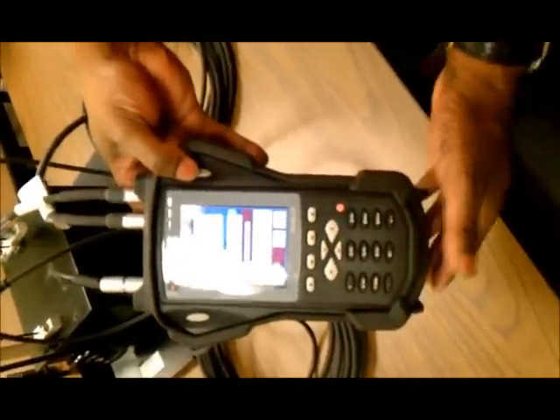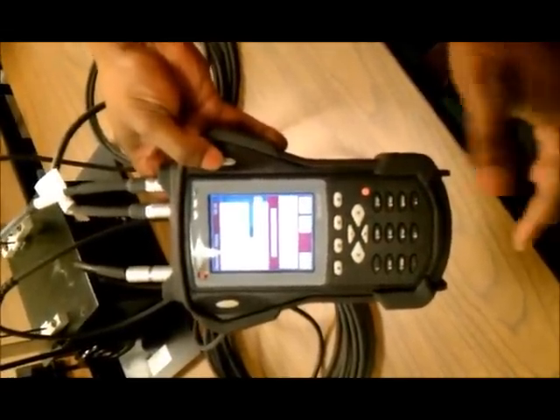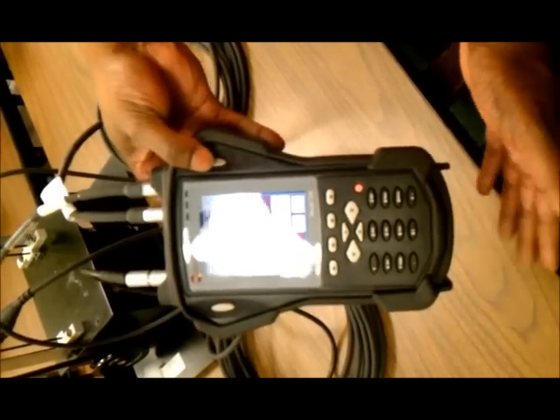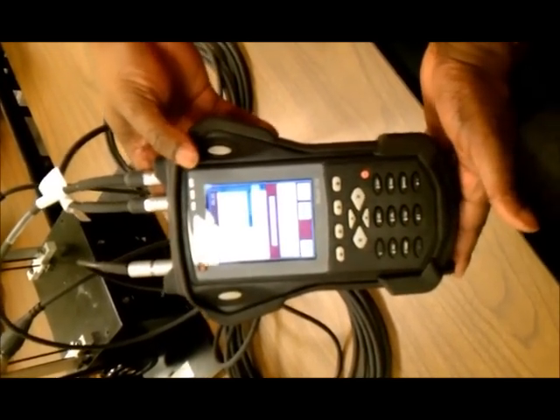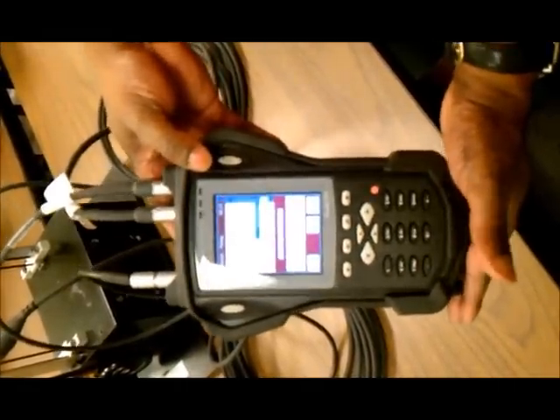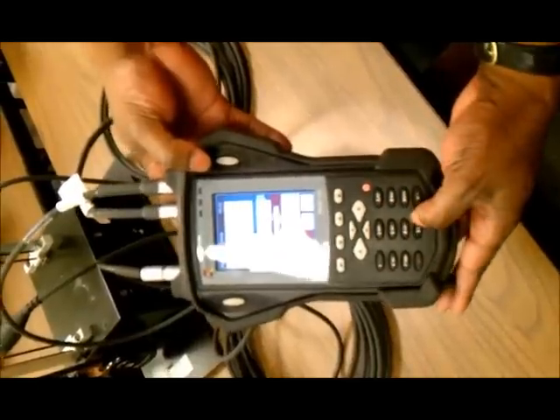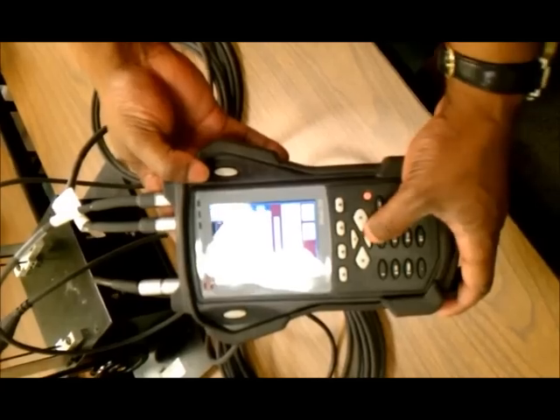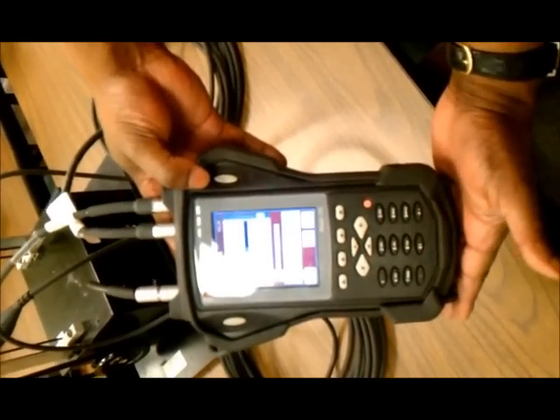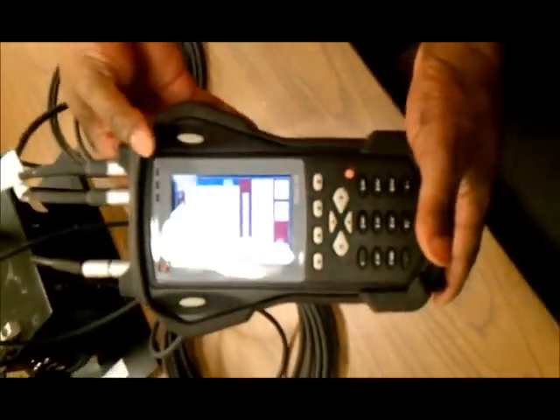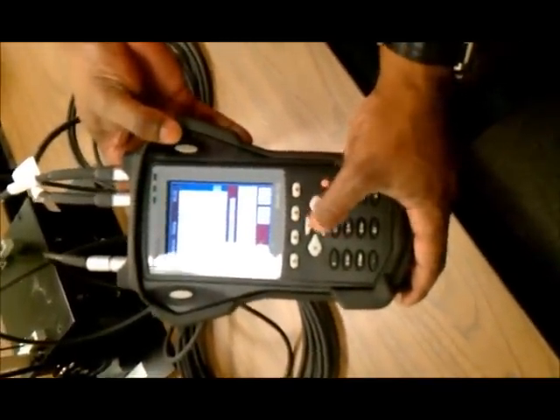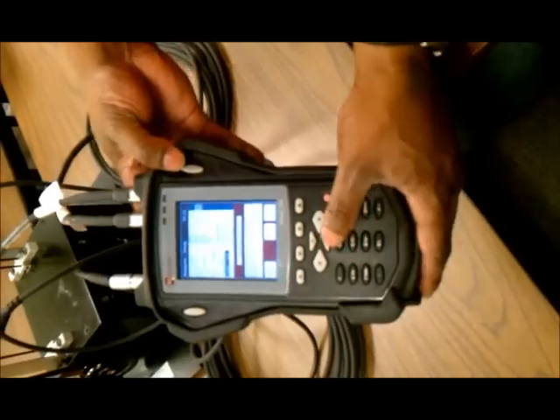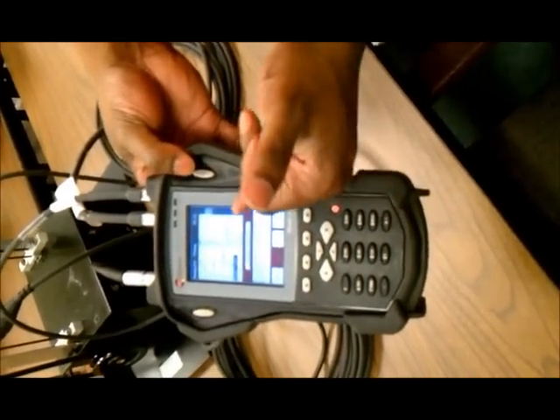And our frequency range is the maximum amount that we'll look at. In this case, we'll put it at 3,000. This instrument right here is capable of 40,000 CPM, or 40,000 hertz as the maximum. So we'll change this to 3,000. And the resolution, we can change that. We have 100, 200, 400, 800, 1600, 3200, 6400, and 12,800. We'll leave it at 400 lines because it's still high resolution, but it doesn't take as long to get the readings.